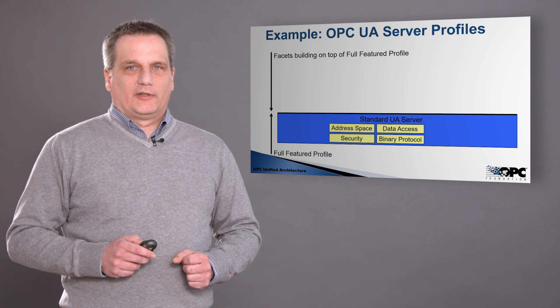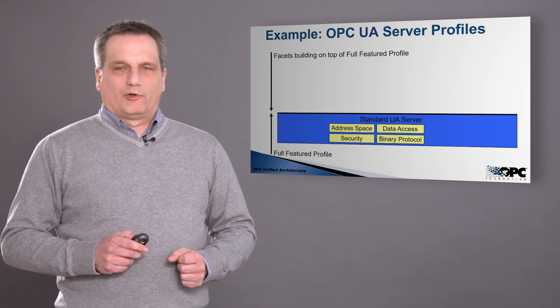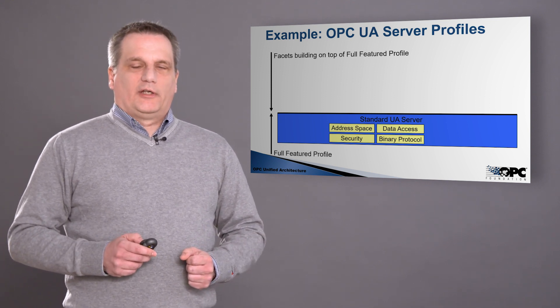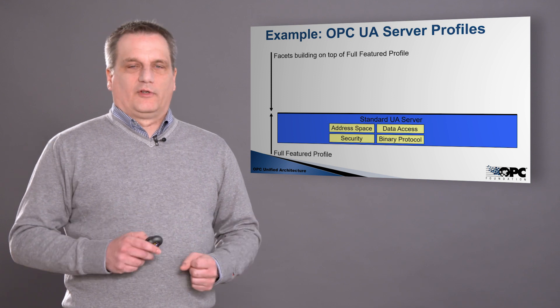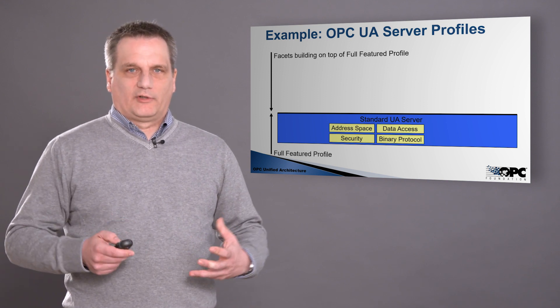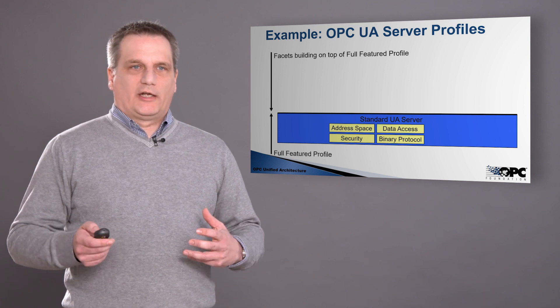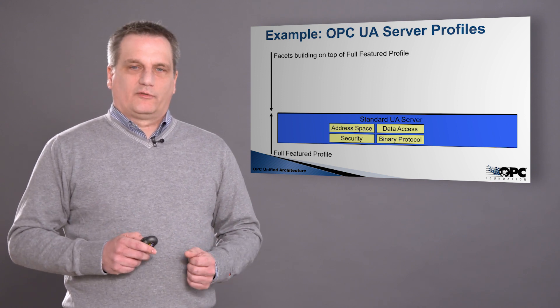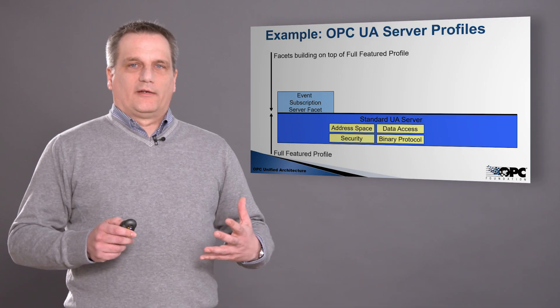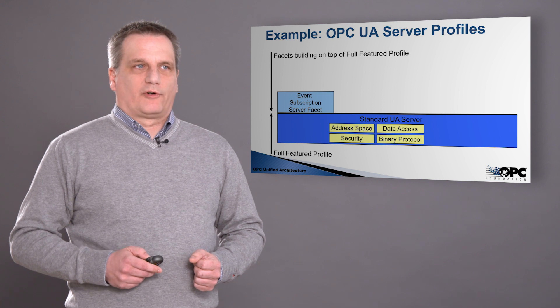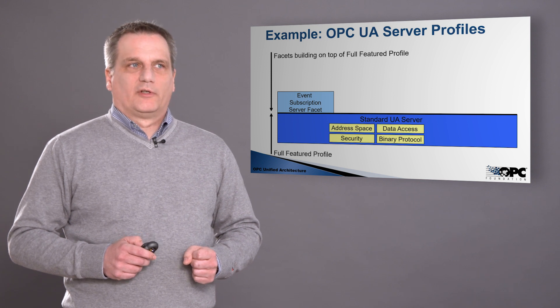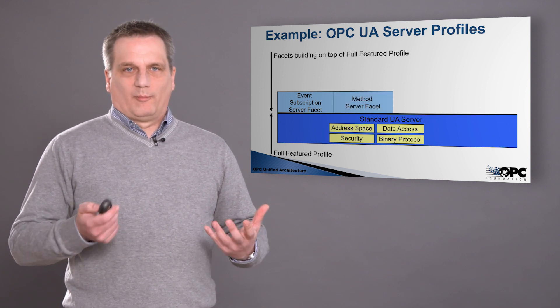As an example, in this picture we have a full featured profile which is a standard UA server. This already contains the address space, it contains security, and it contains data access — so the access to this information: reading, writing, subscribing to data. It also contains the protocol binding, which in this case is the binary TCP protocol. On top of this full featured profile we can have an event subscription facet and a method facet to call methods.